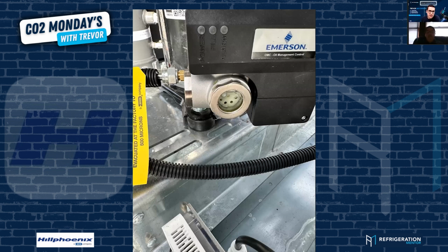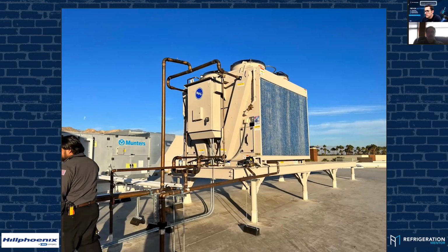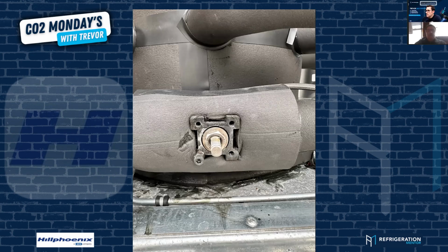A quick question on, I think, the last slide on the drain leg refrigerant piping. Is it preferred to pipe on a run and not bullhead the drain leg together? I do understand the increase in the pipe size. So do you prefer to bullhead or not on the drain leg? So when we bullhead on the drain leg, right here? Yep. Always evenly piped. You know what I mean? You want to make sure it's always symmetrical. If you ran that pipe to the right side to that 90 and had a longer run, even though it is a short distance, there is a difference there. Yep.